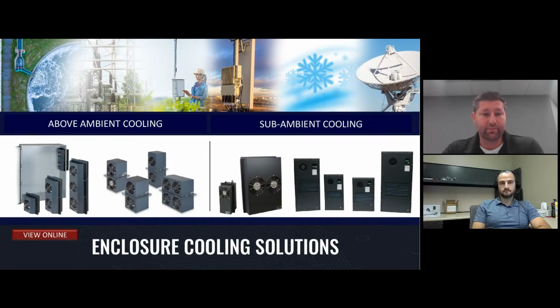The second above-ambient option is our heat pipe cooler. This is a top-mounted solution that uses heat pipes within the core of the heat exchanger to effectively transfer heat. It circulates air inside the cabinet to collect heat, but the heat pipes do the work to transfer it to the outside air. The improved heat pipe conduction area allows a much more compact design, so mounting on top of your system lets you achieve good heat rejection in a compact form factor.